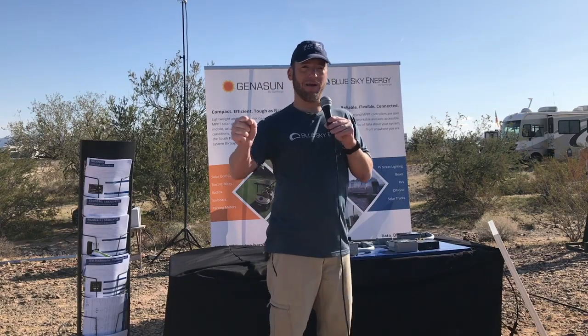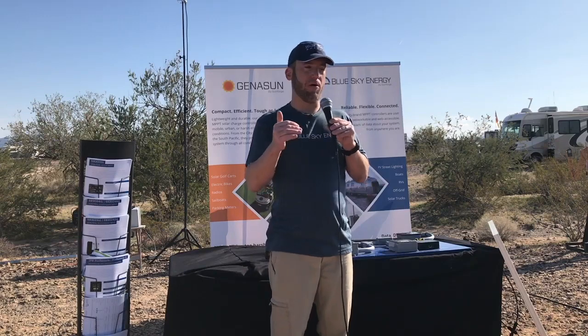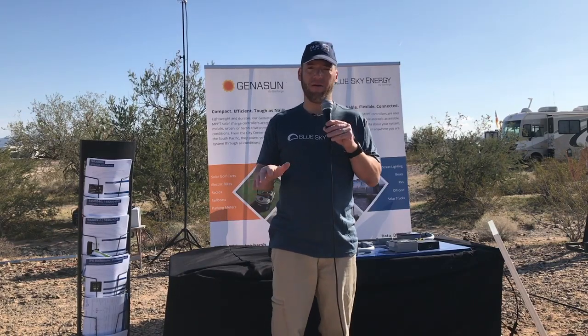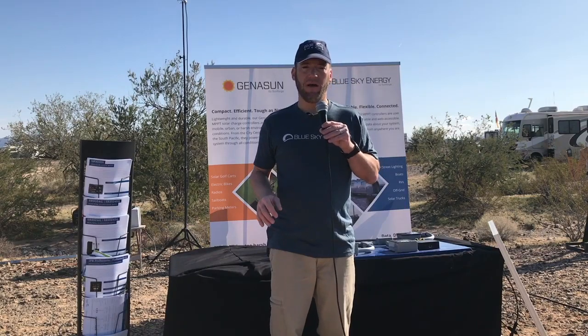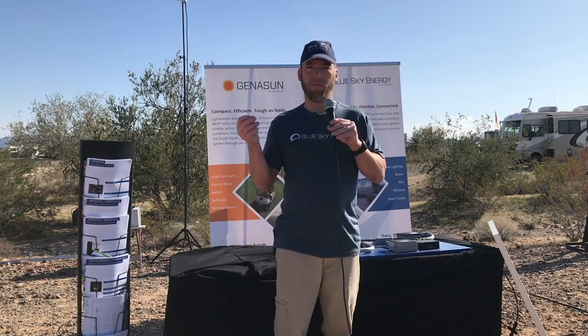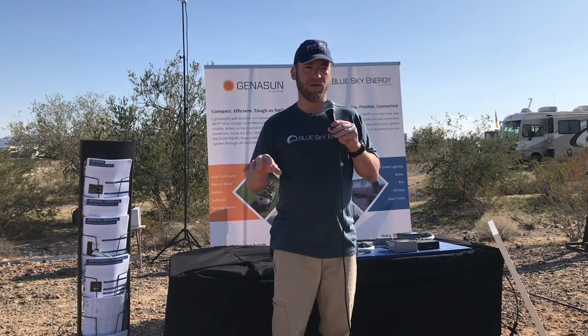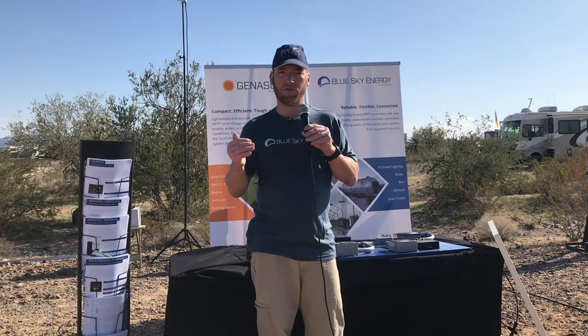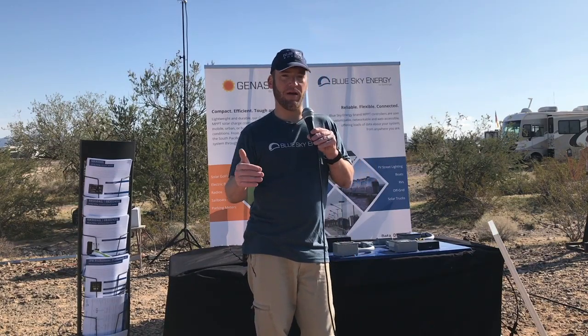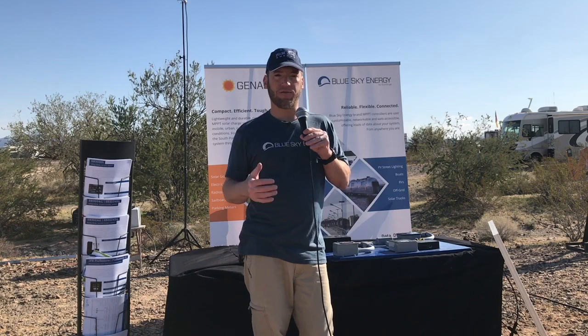If you have a really good lithium battery BMS, you don't want to charge a lithium battery below freezing. You can discharge it below freezing, but you can never charge it if the battery is below 0 degrees Celsius. So a good BMS will also monitor the cell temperature and disconnect charge sources if the battery is below 0 degrees, just for safety's sake.